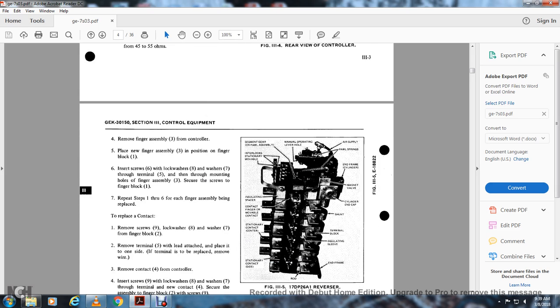Remove the finger assembly 3 from the controller. Place the new finger assembly 3 in the position of the finger block. Insert the 6 screw, lock washer 8, and washer 7 with the terminal 5 through the mounting holes with the finger assembly 3 with the screw to the finger block 1. Repeat steps 1 through 6 for each finger assembly being replaced.